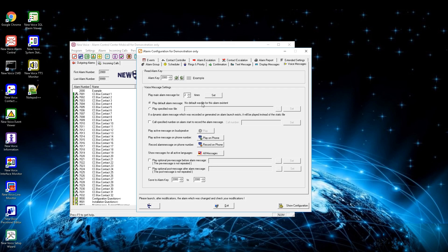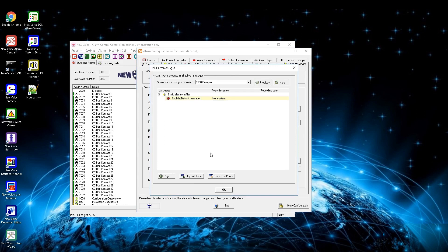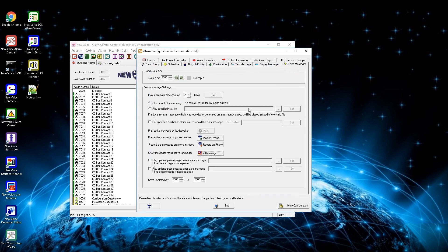Alternatively you can define a specific alarm message below. By activating the next checkbox and entering a number, MobiCall will always call that number at alarm launch and record a message from that phone. Press the button play to hear your current alarm message via speaker, or play on phone to call a phone and hear the alarm message via that phone. Press record on phone to call a phone and record an alarm message for that alarm in the correct format — it will be named correctly and placed in the folder D:\dbv1. Press all messages to see all voice messages for different languages. There is also the possibility to play a pre-message or post-message depending on which checkboxes are active, and both can be activated simultaneously.